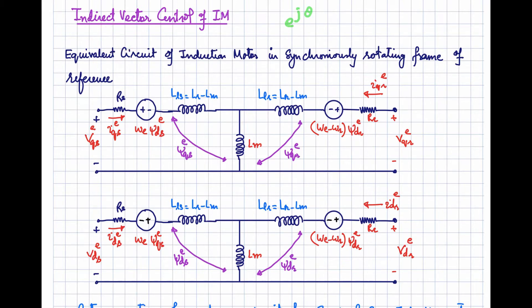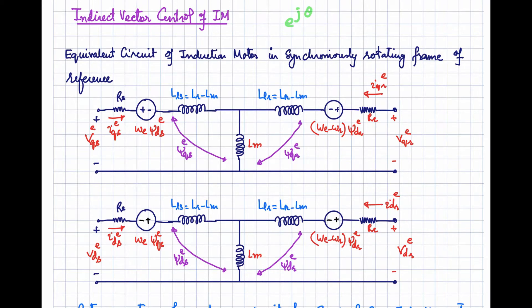In indirect vector control, we use the measured or estimated speed to determine and estimate the rotor flux, and we determine the unit vector from the rotor speed measured from the shaft. The key difference: in direct vector control we use voltage and current signals, whereas in indirect vector control we use the speed obtained from the shaft. For direct vector control, we have seen two methods for estimation of the rotor flux and unit vector in the last two videos.